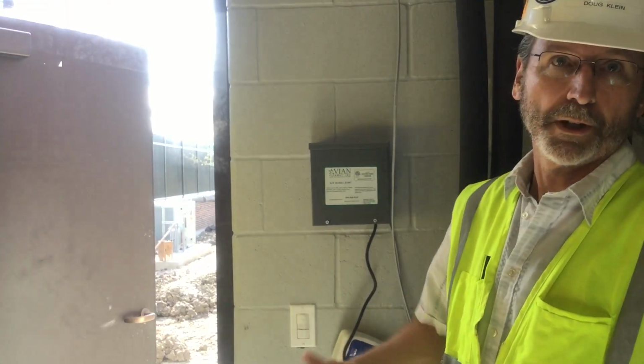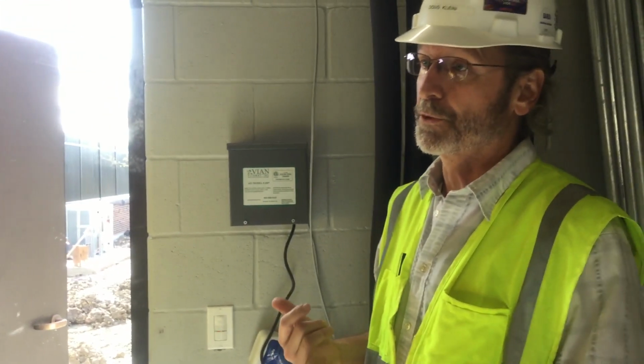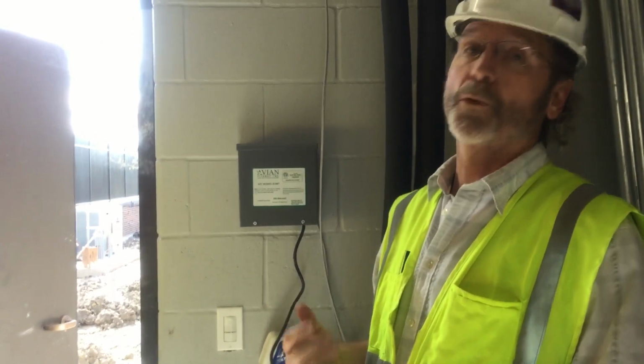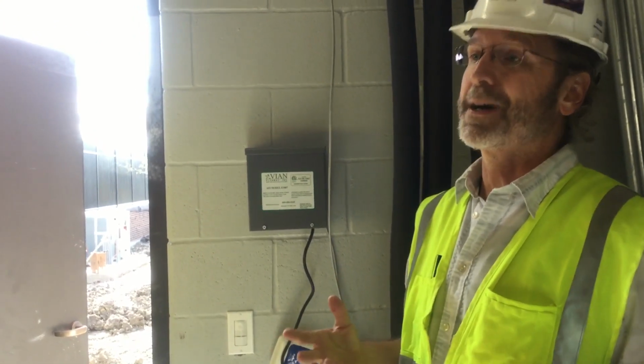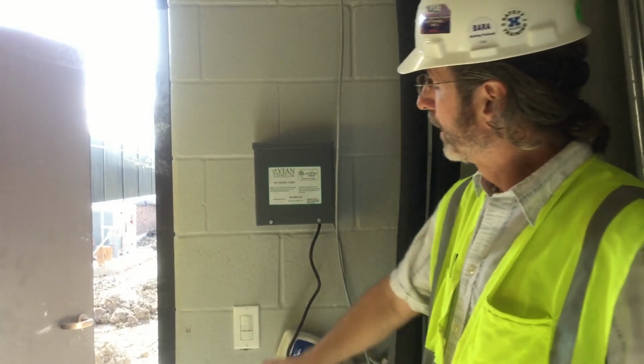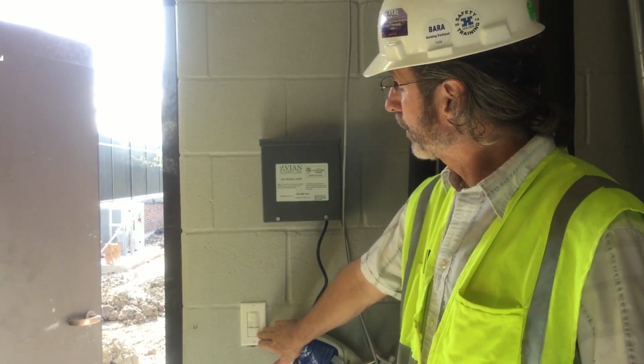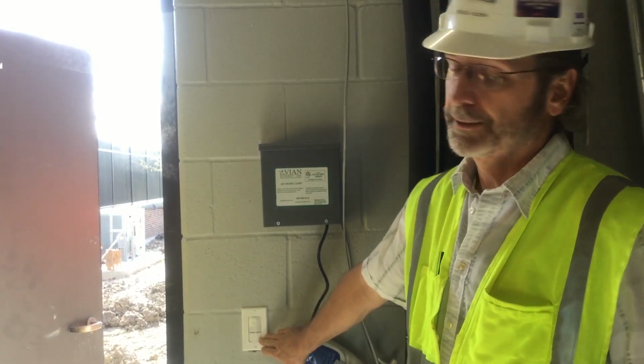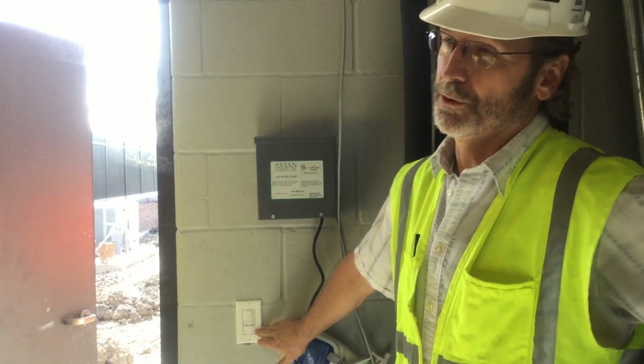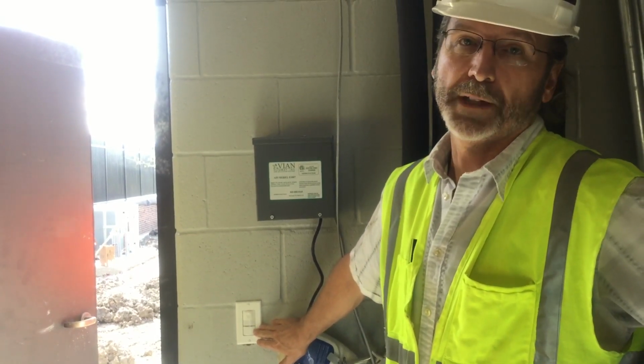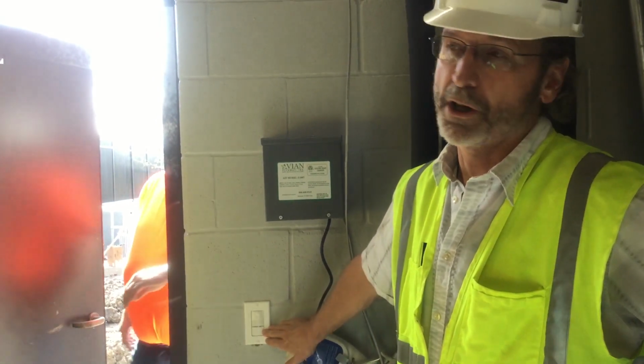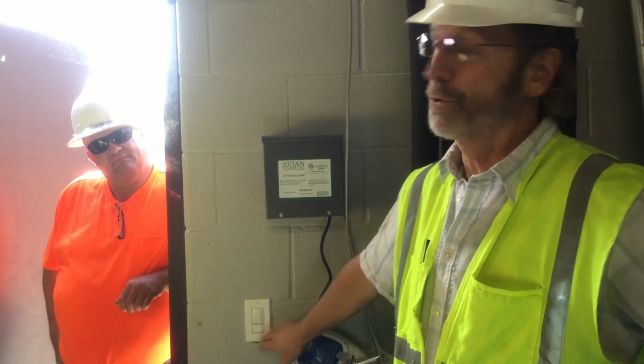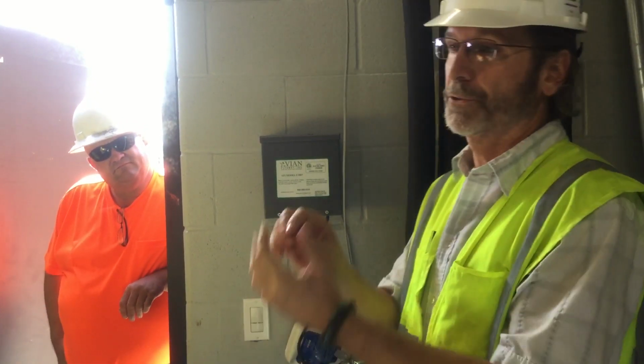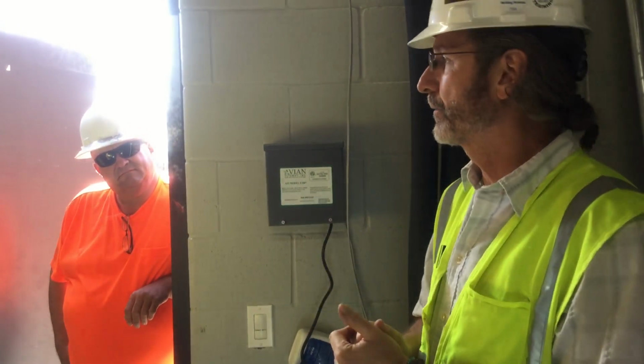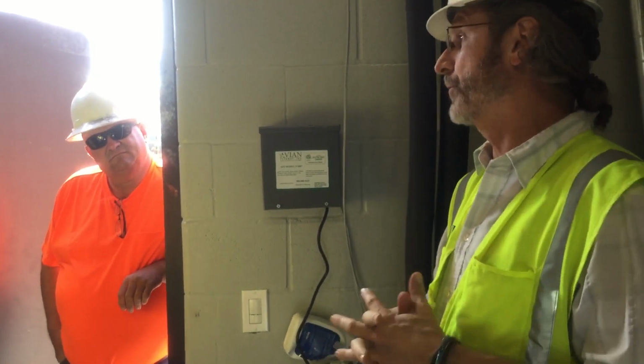This is configurable. It can automatically turn the lights on when you first come in the room, or it can require that when you first come in, nothing happens by itself. You have to press the button. The default configuration, I believe, is manual on. So if you want the lights to automatically start in a room from the sensor, you can do that. You can take the cover off, and there's a dip switch to change that. They're automatically starting.